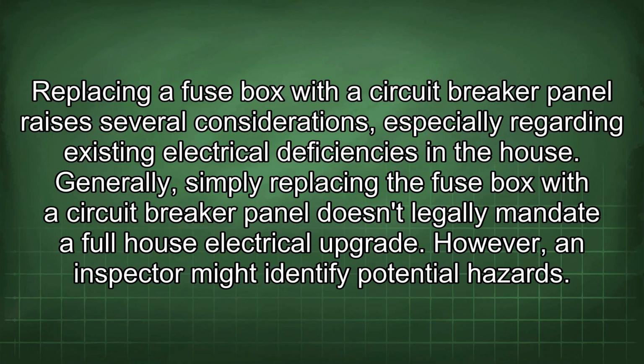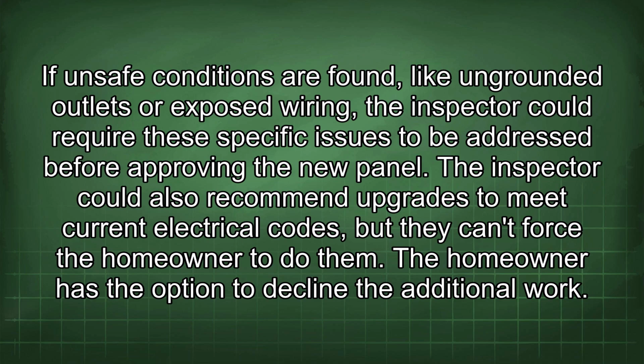Replacing a fuse box with a circuit breaker panel raises several considerations, especially regarding existing electrical deficiencies in the house. Generally, simply replacing the fuse box with a circuit breaker panel doesn't legally mandate a full house electrical upgrade. However, an inspector might identify potential hazards. If unsafe conditions are found, like ungrounded outlets or exposed wiring, the inspector could require these specific issues to be addressed before approving the new panel.